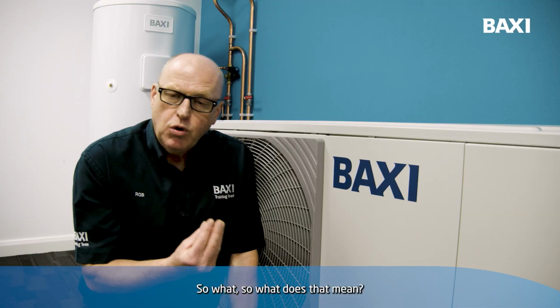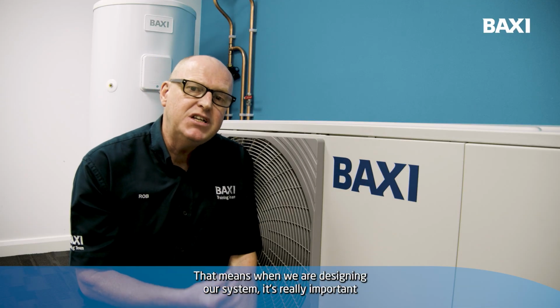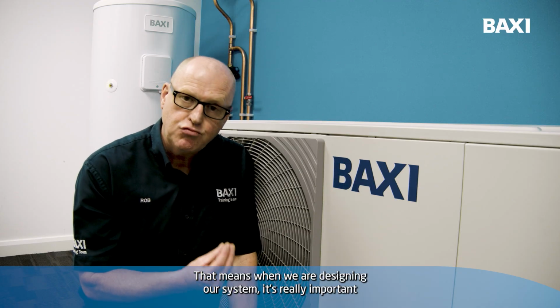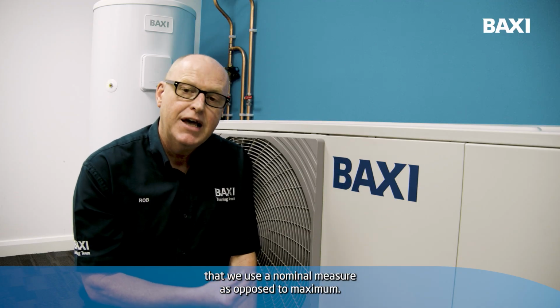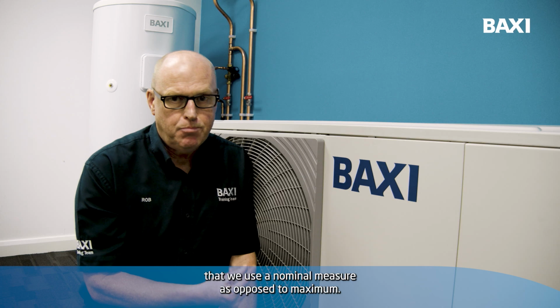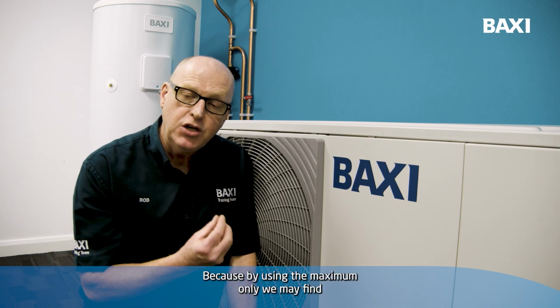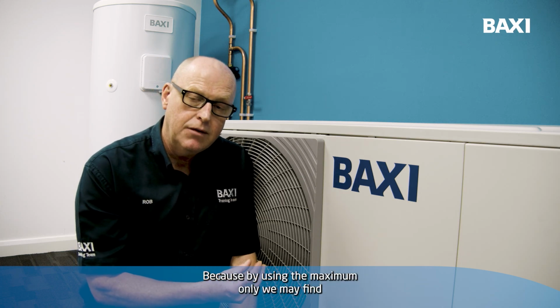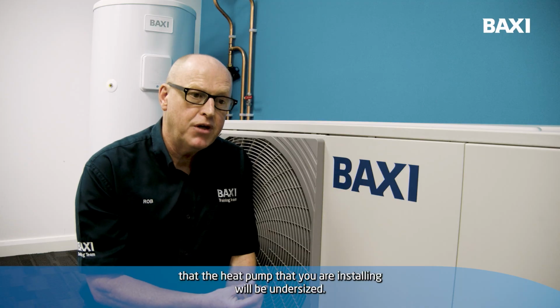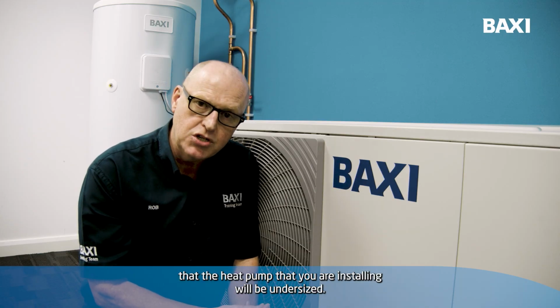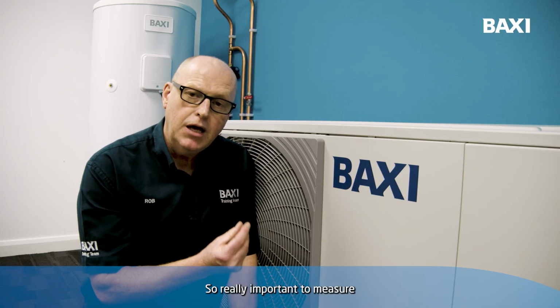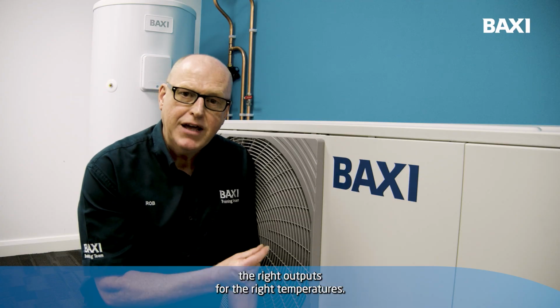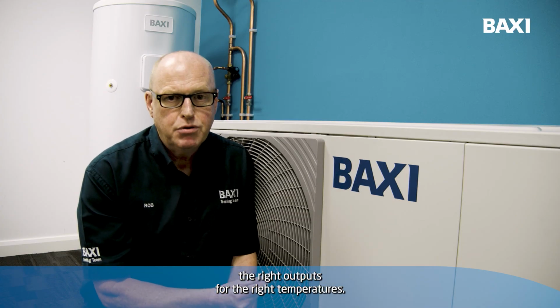So what does that mean? That means when we're designing our system, it's really important that we use a nominal measure as opposed to maximum, because by using the maximum only, we may find that the heat pump that you're installing will be undersized. So really important to measure the right outputs for the right temperatures.